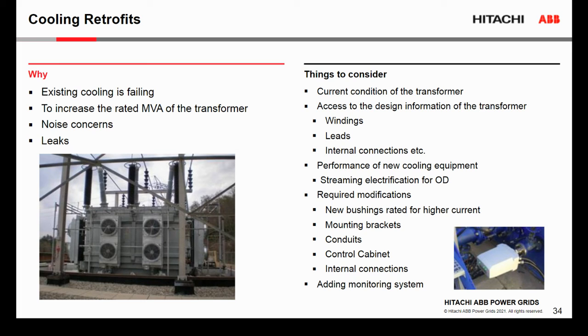We have to also check the performance of the new cooling system, especially when we talk about the OD cooling, where we can face streaming electrification. And then during this modification, we may have to install new bushings for higher current. We may have to install some additional brackets for the cooling system, change the conduits, install additional contactors or devices in the control cabinet, or even add one more control cabinet because the existing one is just too small. We may have to even modify internal connections. And in some cases, we may want to even consider adding a monitoring system like DGA, an online monitoring system.